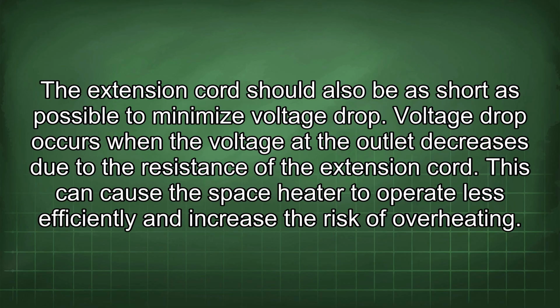The extension cord should also be as short as possible to minimize voltage drop. Voltage drop occurs when the voltage at the outlet decreases due to the resistance of the extension cord, which can cause the space heater to operate less efficiently and increase the risk of overheating.